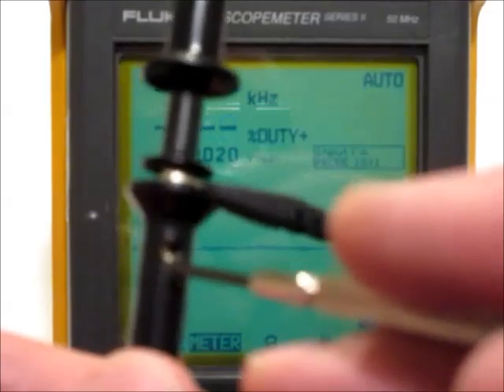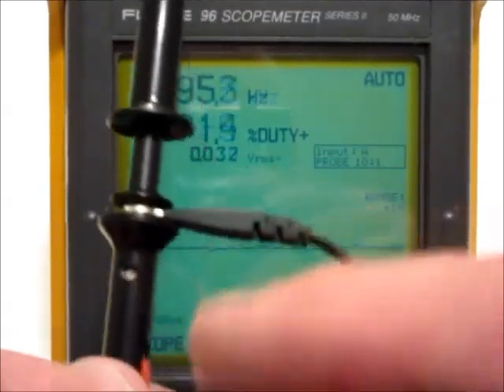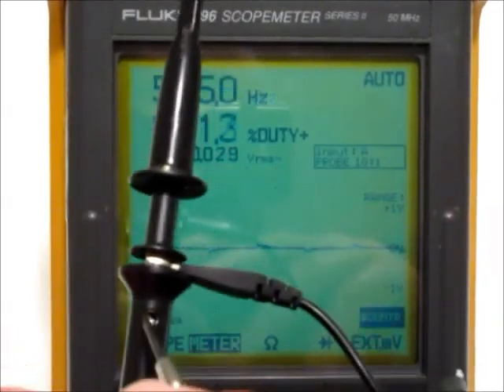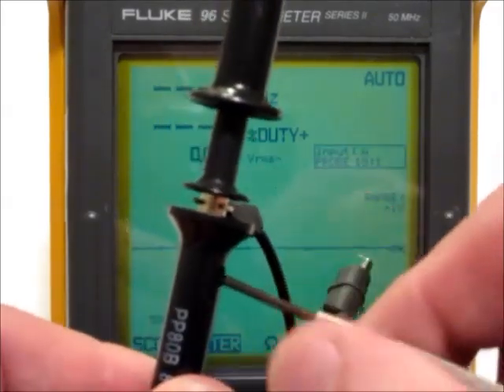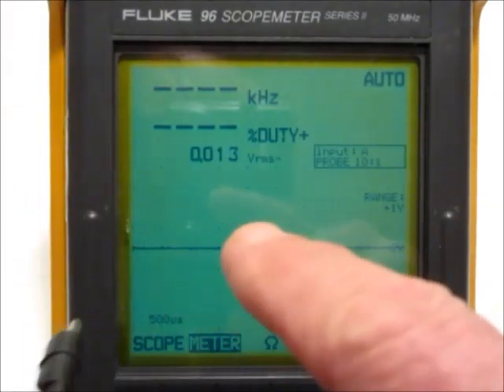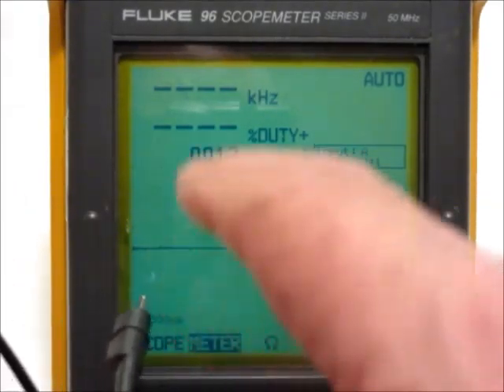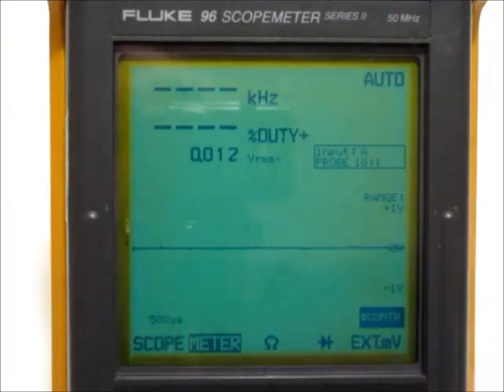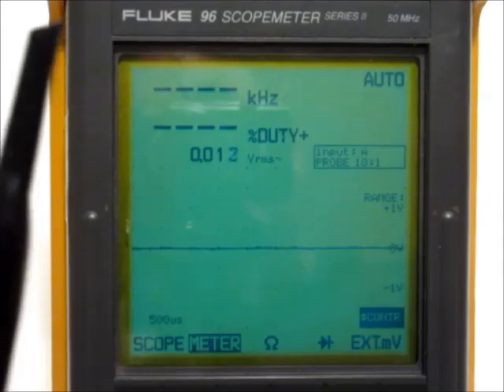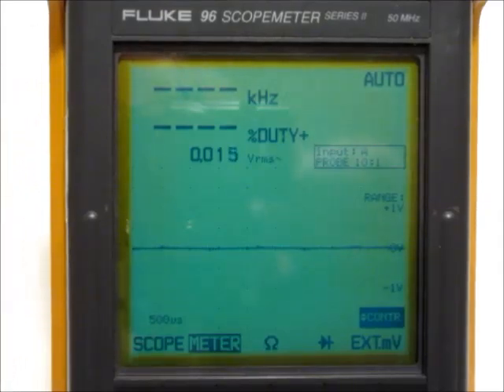Now I'm going to show how you can adjust any probe that has this compensation capacitor right here. You just put a screwdriver in there and turn it while you're looking at the waveform, and you can make it completely flat topped. Now 1,000 hertz is what most manufacturers recommend, that's the frequency of square wave you adjust a probe with. So I'll demonstrate how to do that.